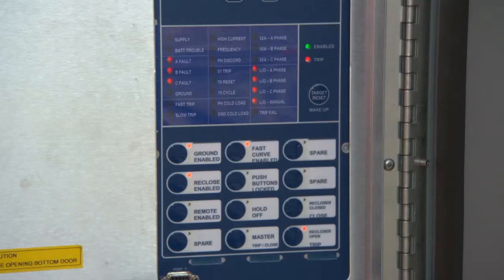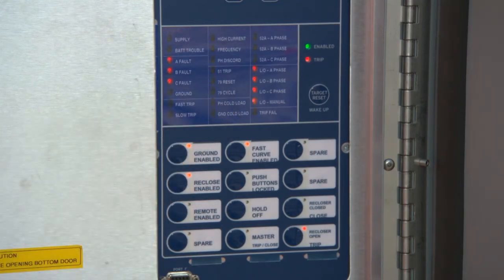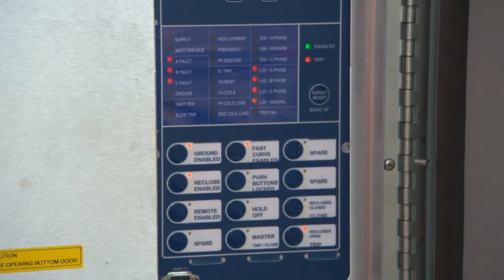If the recloser has tripped out and the red manual lockout LED is on, you will be unable to close the recloser. This will occur if the manual operating handle has either dropped or been pulled down. You'll also notice that all three of the phases are in a lockout state, and their LEDs are red. Now, to close this unit, you must open the cabinet containing the actual reclosers and close in the yellow manual operating handle, which will be in the open or down position.